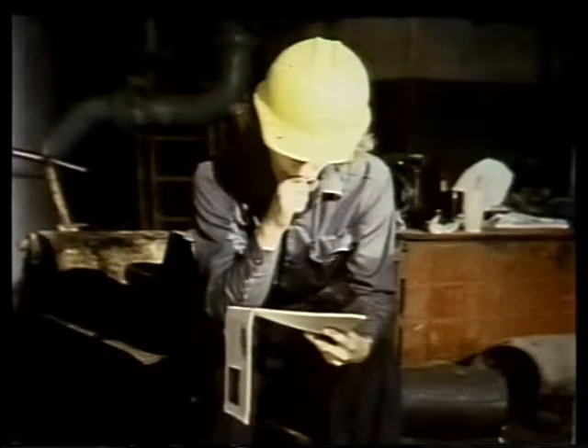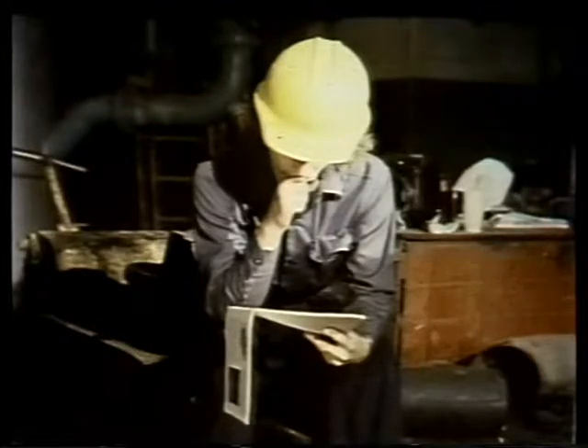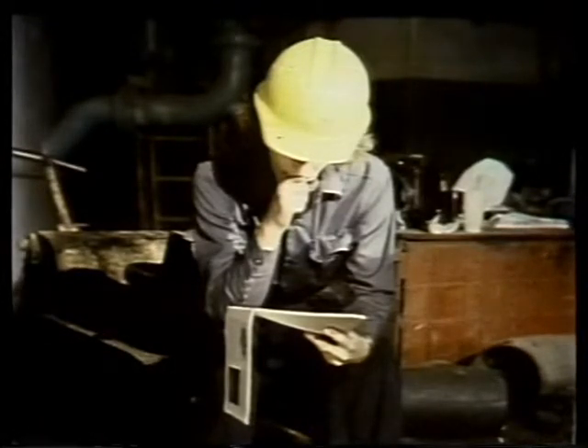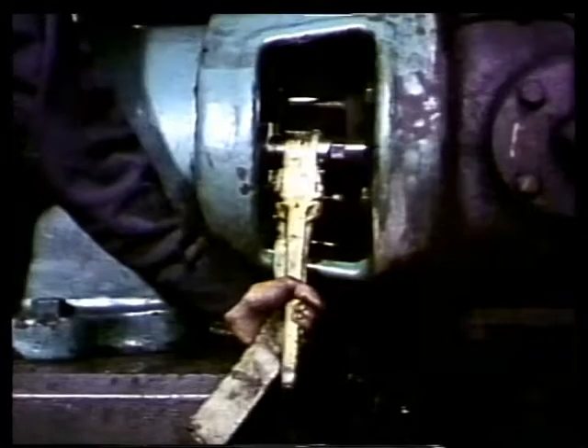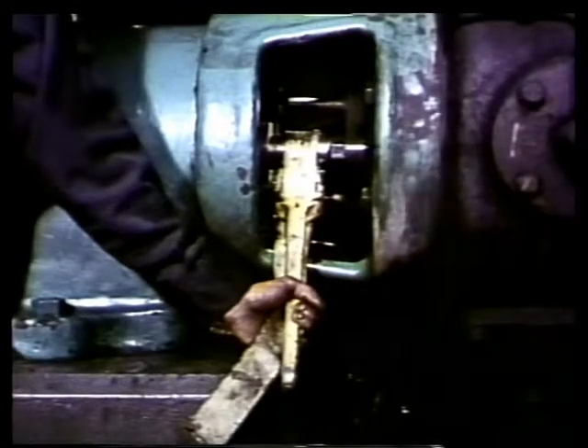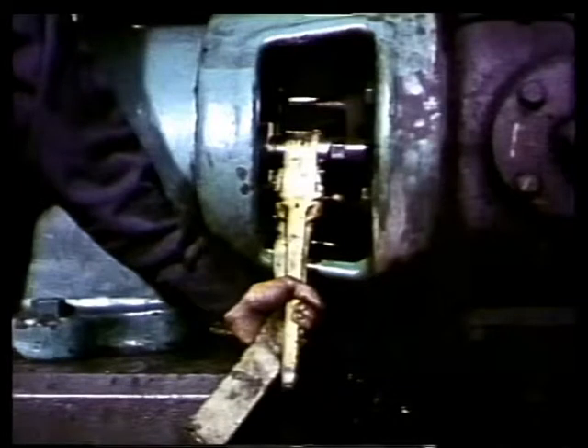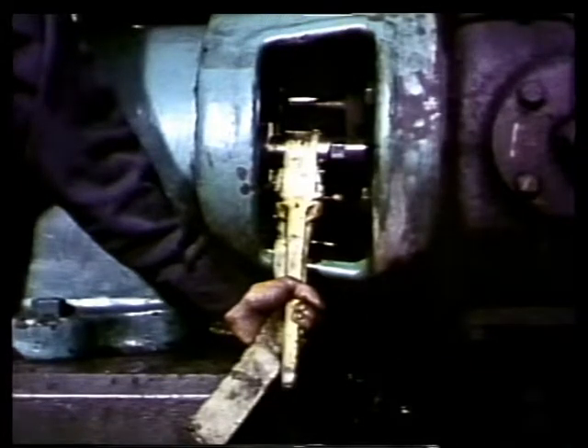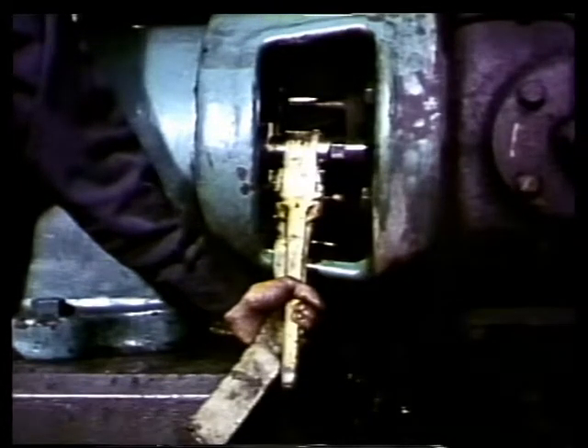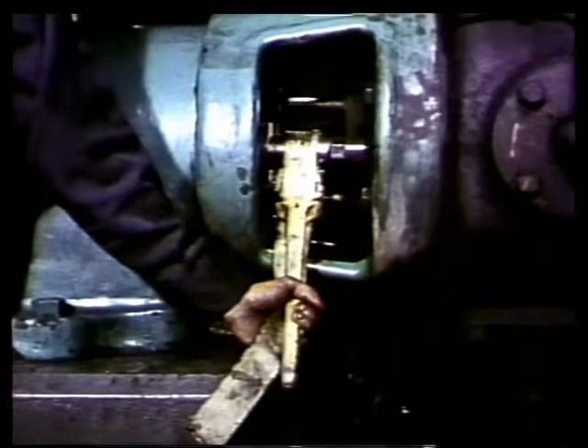Compare the measurement with the specification in the manufacturer's manual and make any necessary adjustments by screwing the piston rod in or out of the crosshead as needed. One way to do this is to attach a strap wrench to the piston rod through the side opening of the compressor. This opening lets you adjust piston end clearances with the head in place.